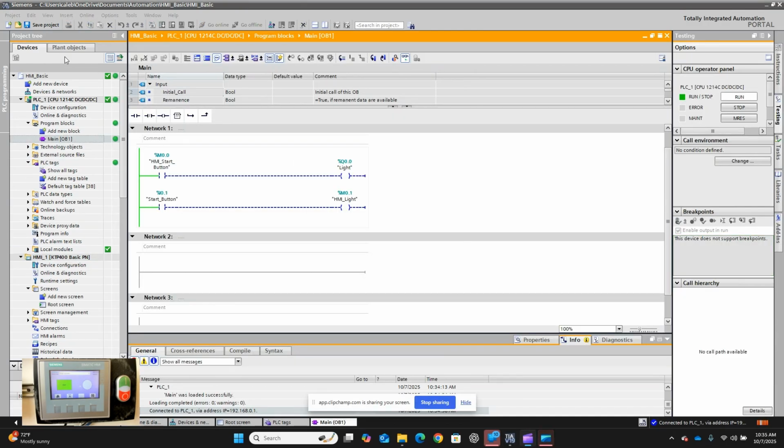So I came up here to our PLC, just like writing PLC, ladder logic, structured text, whatever your preference is. I just did it in main OB1 just because I was making 2 lines of code. I dragged contacts down. I assigned the tags. I made it here so that a virtual button turns on a physical light and a physical button turns on a virtual light, just to show the back and forth. So I downloaded. I went online. We already downloaded to this HMI.